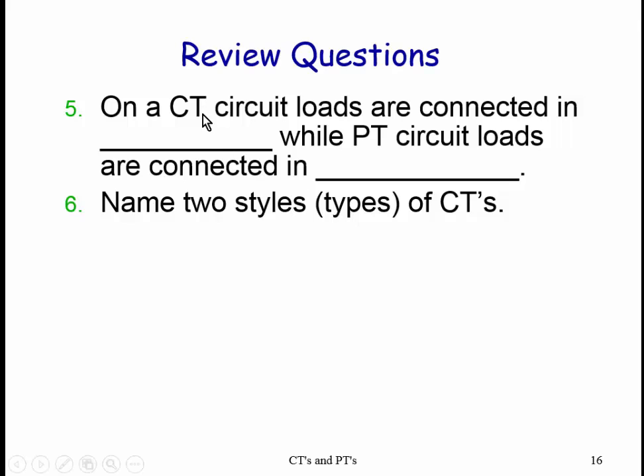Okay. CT circuit loads are connected in series, while PT circuits are connected in parallel. So the CTs are really a lot different than voltage transformers. You connect the loads in series instead of parallel. You short them instead of opening them. And they maintain a steady current, not a steady voltage. And then some different styles. We looked at window type, and we looked at bar type, and we looked at bagel type. There's all kinds of different configurations.